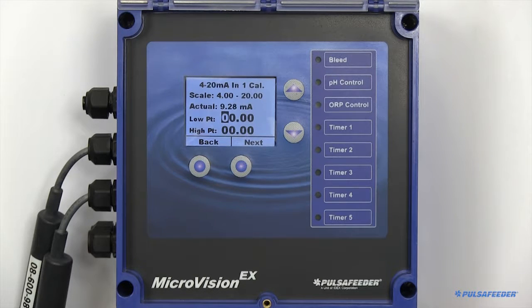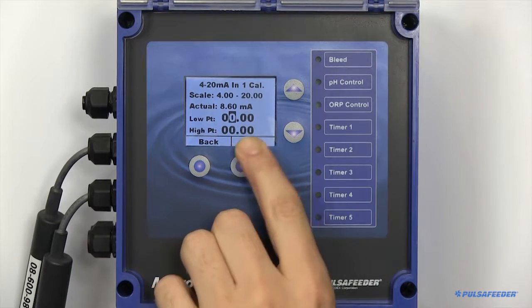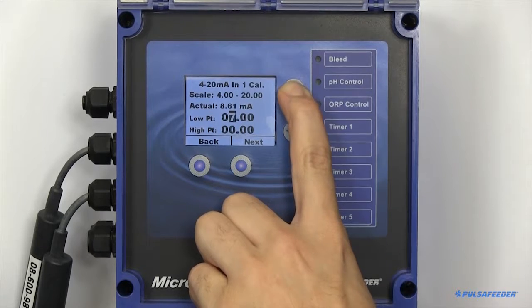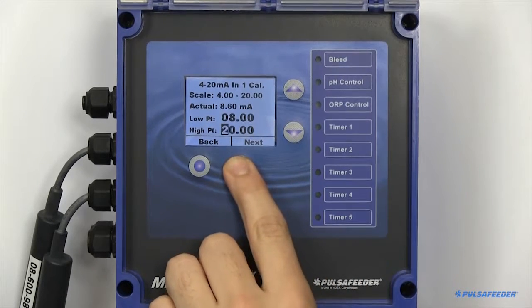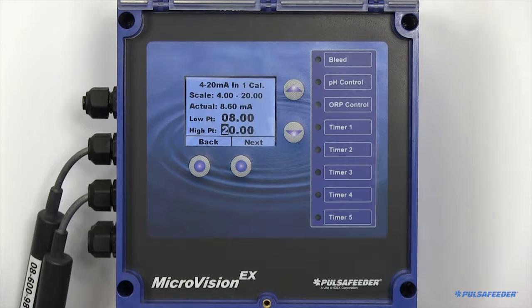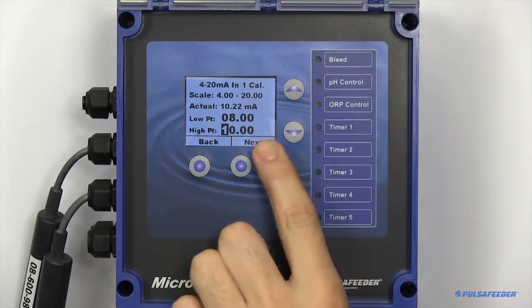Place your probe in its low buffer solution. Wait for the unit to adjust, enter the correlating value into the controller, and enter through just the top row. Next, place your probe in your high buffer solution. Wait for your unit to adjust again. Enter the correlating value, and then enter through the bottom row. Your 4 to 20 input board should now be configured.